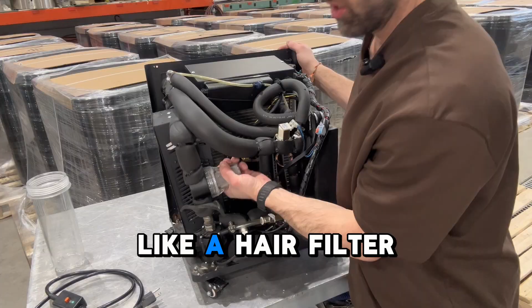Now here's something interesting. There's an internal filter, like a hair filter, placed inside the unit before the main external filter. But the problem is, once it gets clogged, the only way to access it is to completely disassemble the chiller.